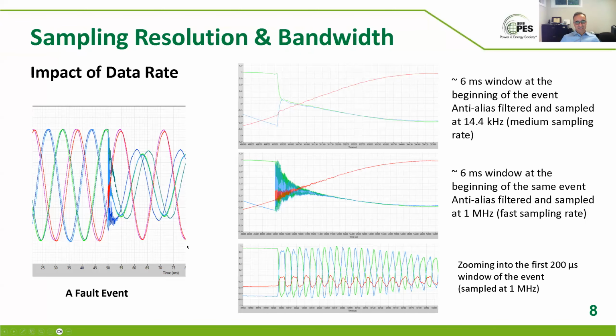And just a little bit of illustration here to show what gets lost. Many of you have done digital signal processing, so this is obvious, but sometimes we forget that when you sample at a lower frequency, you could miss certain things. This is an actual recorded waveform from the 2 ends of a roughly 25 kilometer line during a fault. You see a cycle and a half before the fault, with 6 traces. Reds are phase A, blues are phase B and greens are phase C. The light colors are one side and the darker ones are the other side.